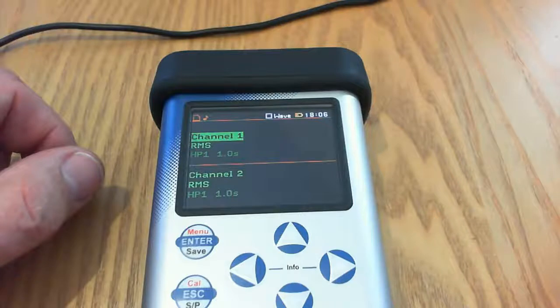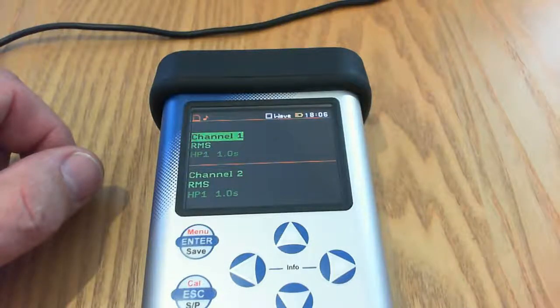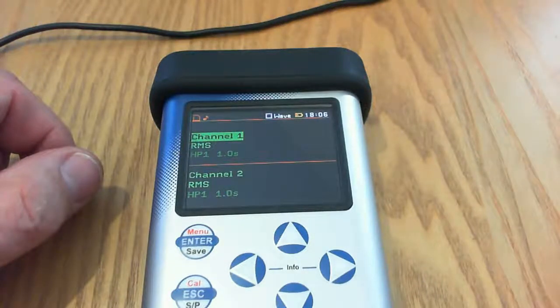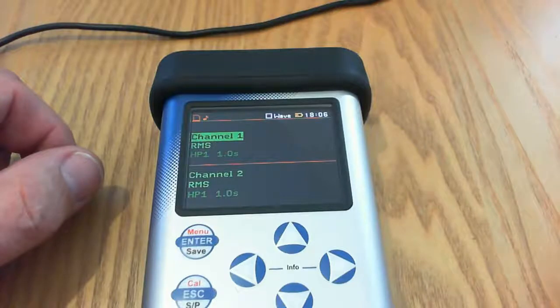The next thing you do is obviously set up your normal measurement parameters. For example, vibration in channels 1, 2 and 3 might be using WD or WB weighting, and then set up your profiles in channel 4 for your noise measurement. I won't go into that now.